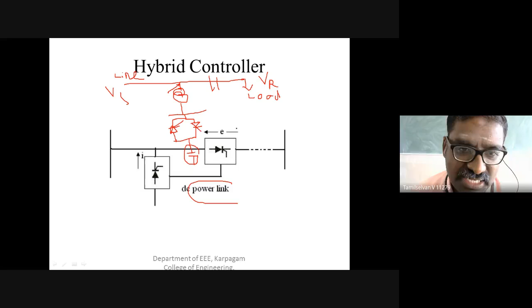So likewise, each and every FACTS device or FACTS controller has its own controlled parameter. Based on that, we can say how about your hybrid, shunt and series controller - remember that is going to be called a unified power flow controller. It means it will control current, voltage, impedance, and power. That fourth quadrant is going to be called the unified power flow controller.